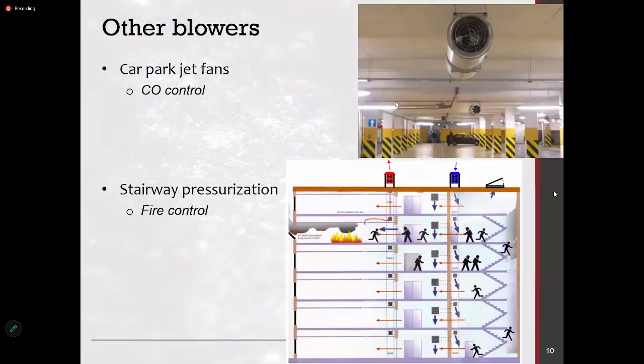So we were actually looking at these jet fans, where you can operate them depending on the carbon monoxide level. So if the carbon monoxide levels are not that high, you need not operate them, because the fans would be running in vain and there is no purpose.